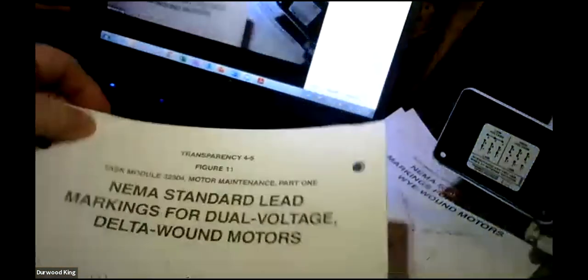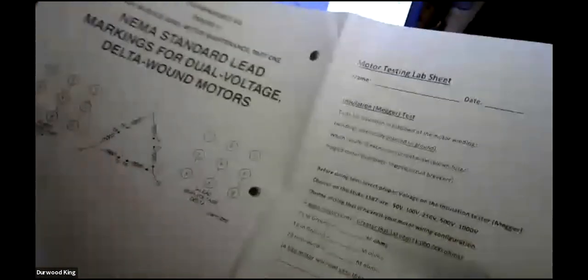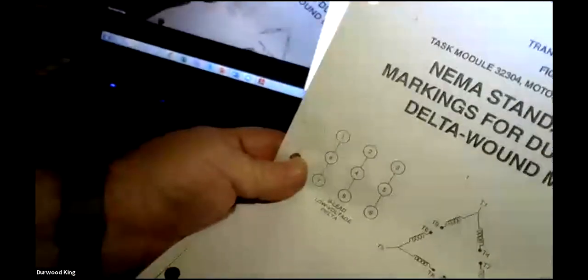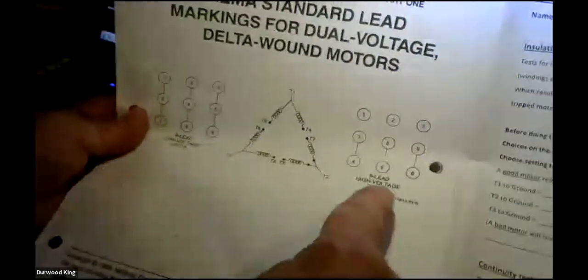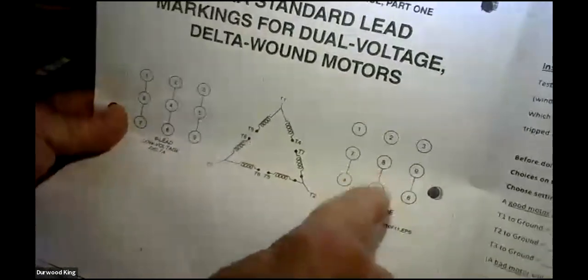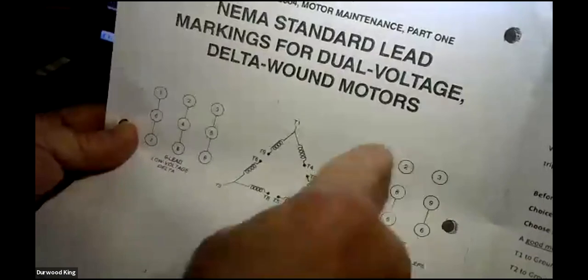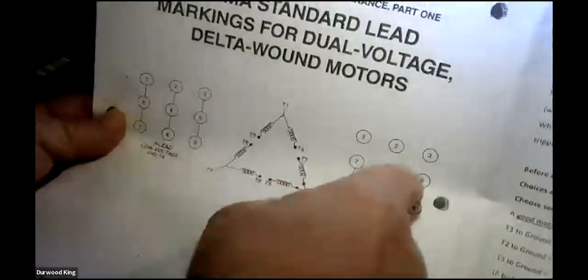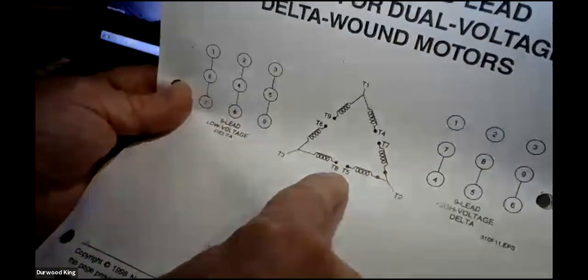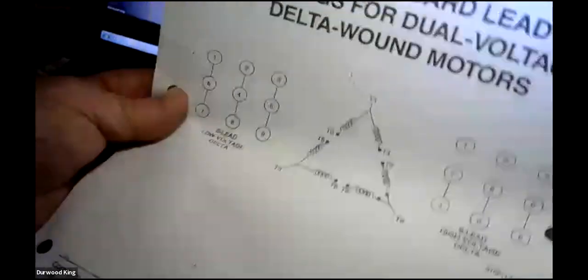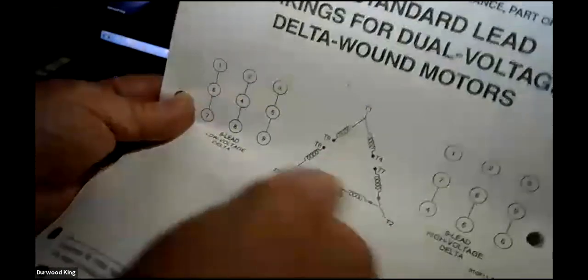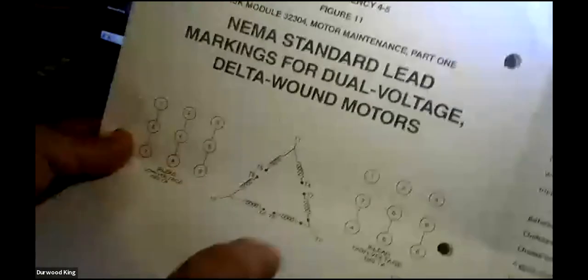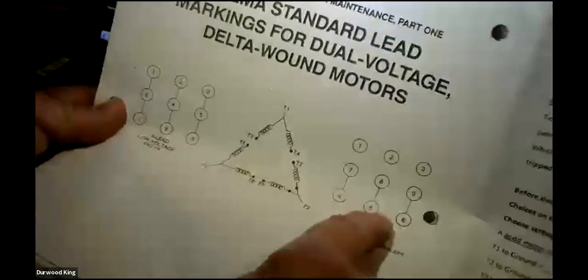The other one I sent you is actually on Delta. Now, one thing about Delta, and once I say that, I'm going to close because I know it's getting late. The Delta sheet does the same test right here. What I would do is wire the Delta on high voltage. When you do that, you test 1, 2, and 3 to ground. You put 4 and 7 together, 5 and 8, and 6 and 9. You put wire nuts in there, and it gives you a series delta. All these are in series, and it forms a single delta. Then you check each lead to ground with your insulation tester like we just did, and that's how you check a delta motor on high voltage.